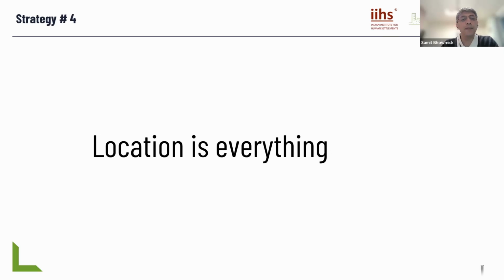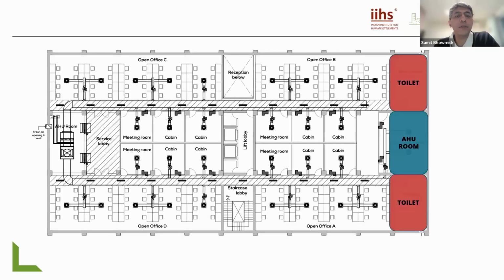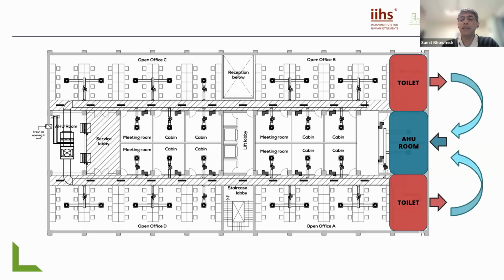Take a look at this small office space, very simple and straightforward, with an AHU room on one side and the toilets also on the same side. A lot of architects might prefer this because it's more compact, with services aligned on one side. But this has the problem that the exhaust from the toilets might get short cycled into the fresh air intakes of the AHUs.